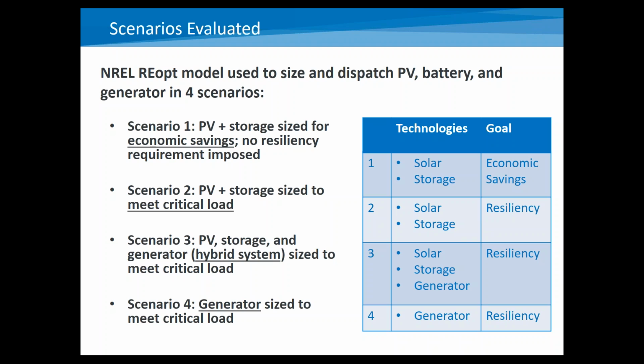In scenario three, we then added a generator to the potential technologies that could sustain the critical load during this outage. So we looked at PV storage and a generator hybrid system, again, sized to meet that critical load during the outage. And in all of these cases, in scenarios two, three, and four, the systems meet the critical load during the outage, but then they can also operate for economic gain while the system is grid connected. Scenario four was somewhat of a comparison scenario, so we looked at a generator only, which is typically what most buildings in New York City that have backup power have right now, just a generator sized to meet the critical load.